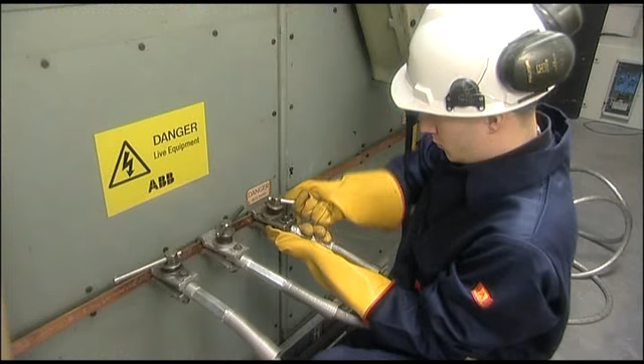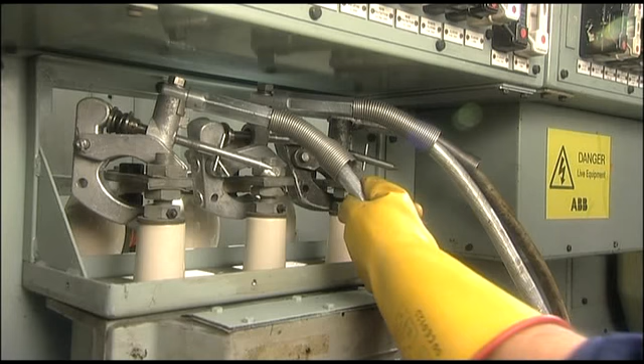A number of earths may be applied between any source of supply and the point of work. Circuit breakers and switches usually have a facility to earth the equipment. If possible, earth the part that is being worked on, or at least make sure the earth is visible from where the work is being carried out.